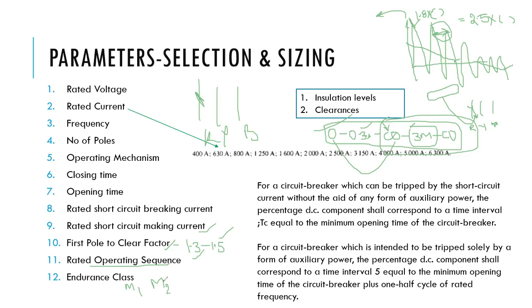It again depends upon the requirement, how frequently you are opening or closing the breakers. From your past historical data, you can see the number of operations generally seen in your last projects. So I feel M2 is a better one for me compared to M3 and M1.